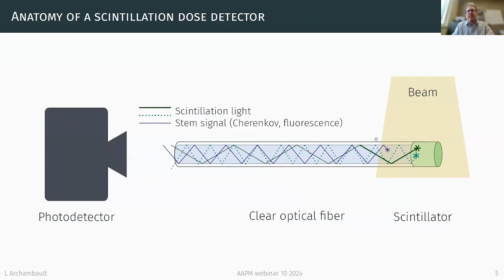One common problem with plastic scintillation detectors is that when you irradiate, you cannot just irradiate the scintillator itself, you also irradiate the optical fiber, the stem, and that also generates some light. It can happen through Cherenkov radiation or fluorescence. And that has been a problem for many years for scintillation dosimetry. So what we get in terms of wavelength here is both the scintillation that you see in blue and the Cherenkov and/or fluorescence that you see in red. What we are interested in is just the blue curve, but these two spectra overlap, and it's impossible to filter just one.